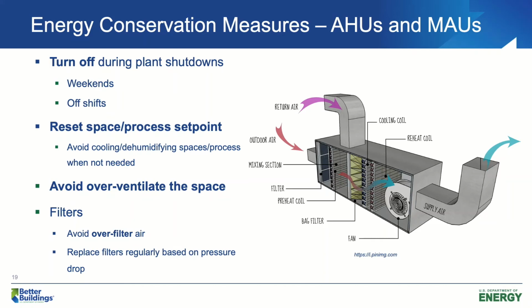The same idea applies for filters. Are we using the correct type of filters? Do we really need MERV 16 for our applications? Can MERV 13 do the job? The idea is that we would like to avoid over cleaning the air. If we can, we also recommend replacing filters regularly to make sure that we are not getting too much pressure loss across filters.